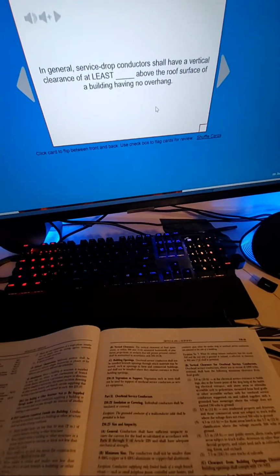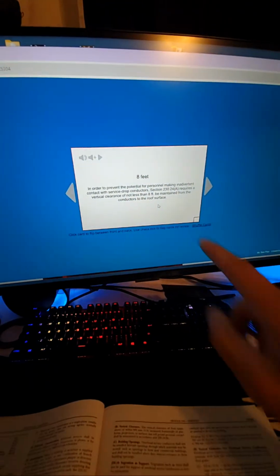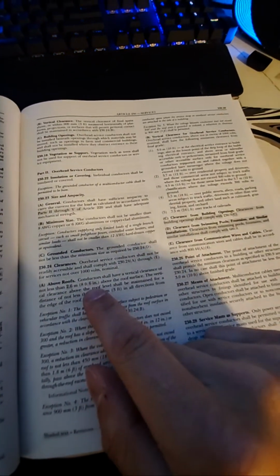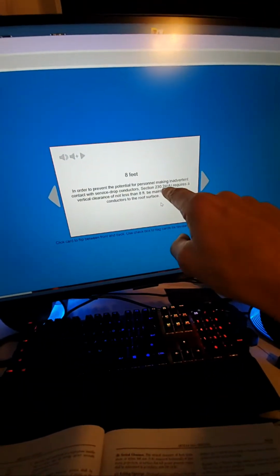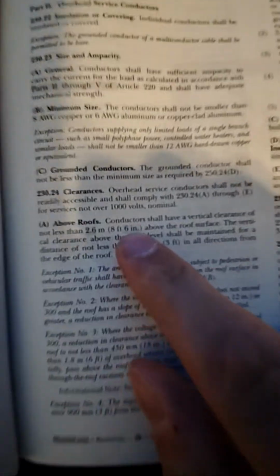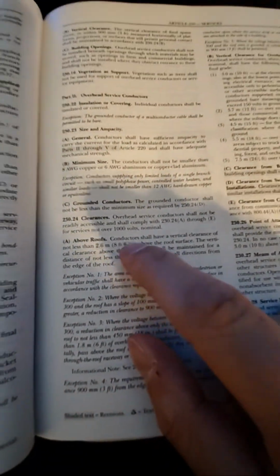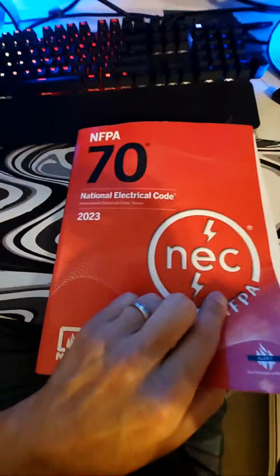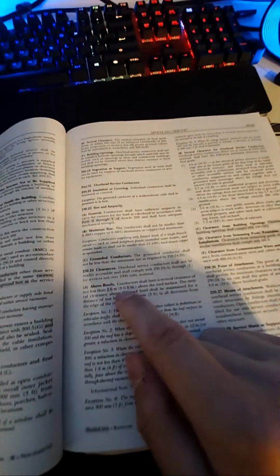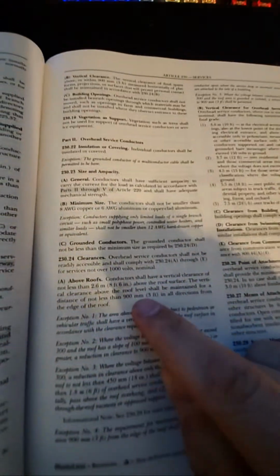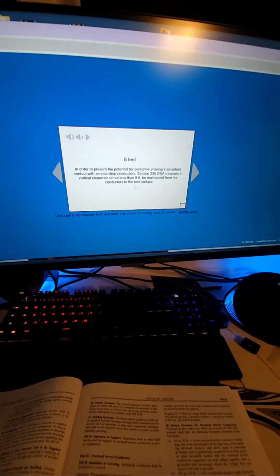How do I get the answer? It says 8 feet. They might have changed it, but this is going to be where you get the answer. Is it A? It might tell us, yeah, 230.24(A). Interesting. You can see where it's highlighted right there. That means that it is a change. So in the 2023, you can see where the highlights are, typically new information, I believe, and they italicized that. I'd have to look at that for sure, but with the highlighted stuff, it's usually a change. So we found the answer there, and 8 foot 6 is the answer.